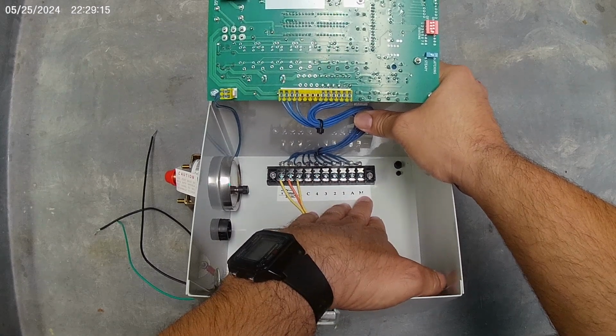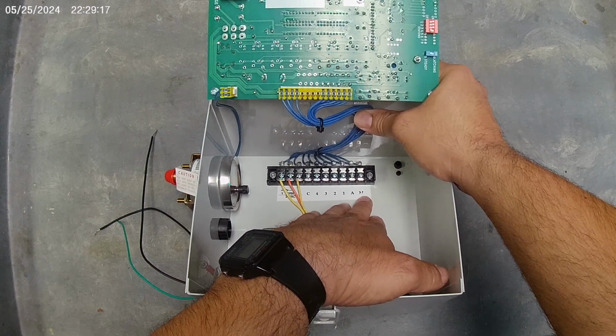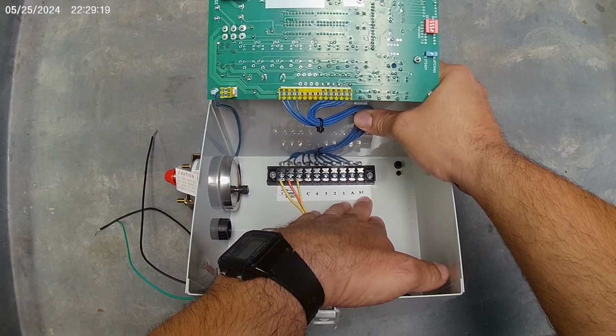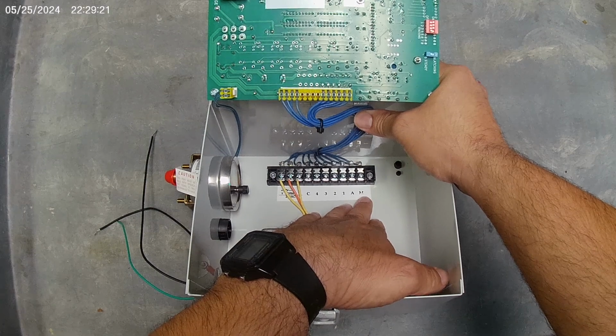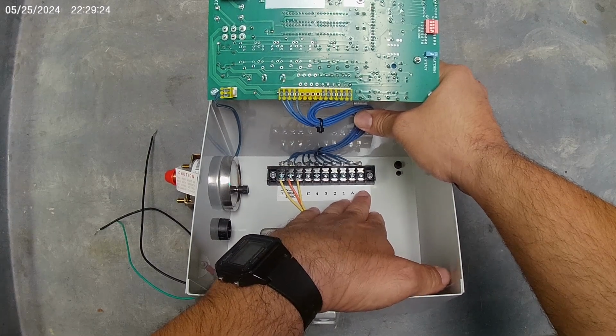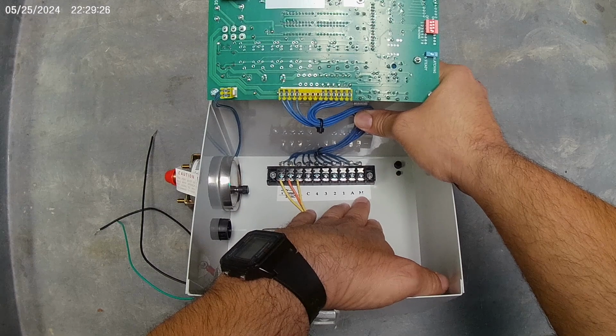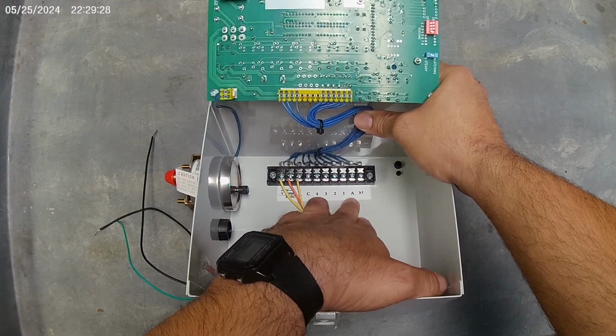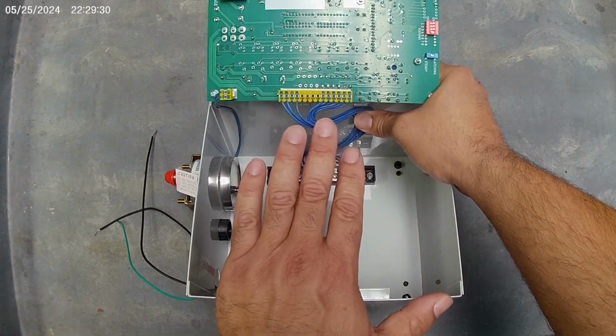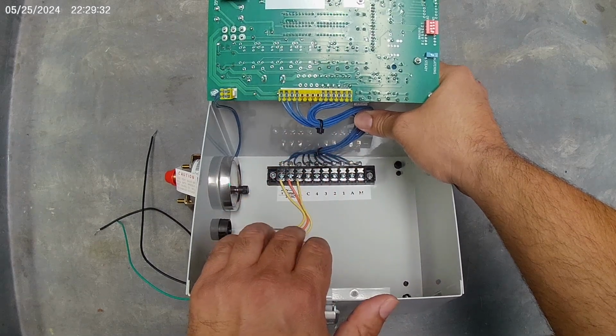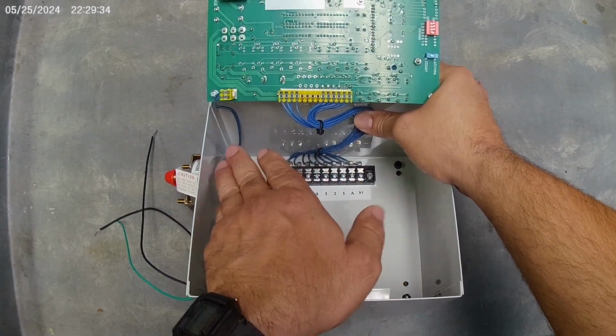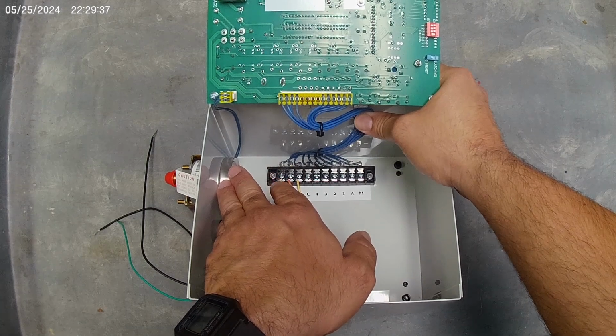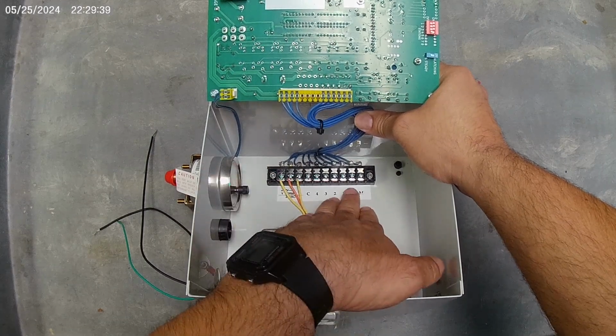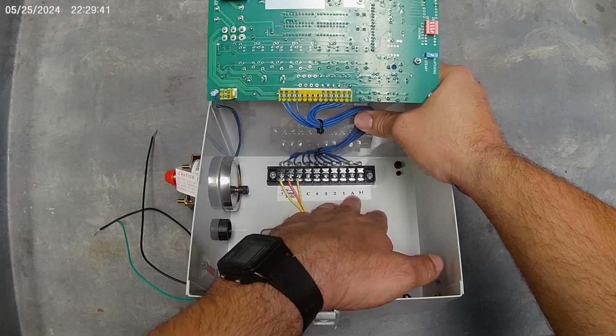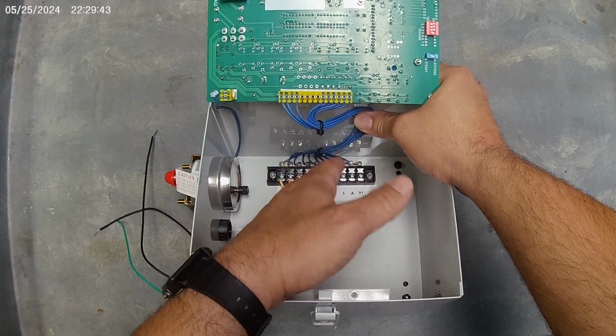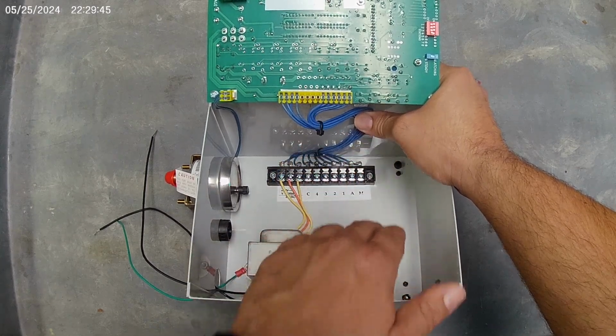Master is for a pressure sustaining valve, so if we have limited flow and we want to close the outlet of our filters to the field to build up enough pressure to backflush, we would put an electric valve there and operate that here. Alarm is a feature where if this controller backflushes 3 times consecutively off of pressure only without going back to normal operation in between, this output will turn on so we can have a light or something and notify someone that there may be a problem with the system.